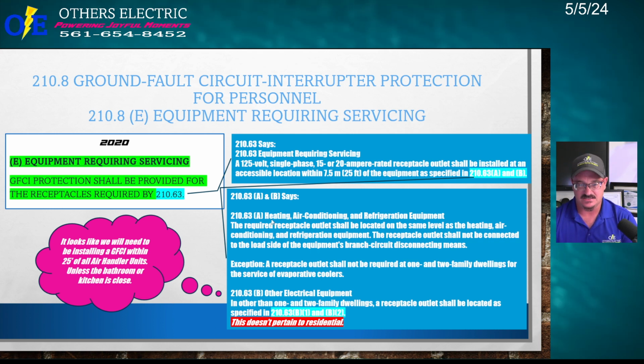Ready? 210.63A says heating, air conditioning, and refrigeration equipment. The required receptacle outlet shall be located on the same level as the heating, air conditioning, and refrigeration equipment. The receptacle outlet shall not be connected to the load side of the equipment branch circuit disconnecting means. So, what are they saying there? If you have an outdoor piece of AC equipment, your condensing unit, you need to have a GFCI within 25 foot of that. Okay? And it cannot be connected to the load side of a disconnecting means. So if you've got a disconnect that shuts down the AC unit, that disconnect is not allowed to shut down the GFI. Okay? So that's a code that is added.